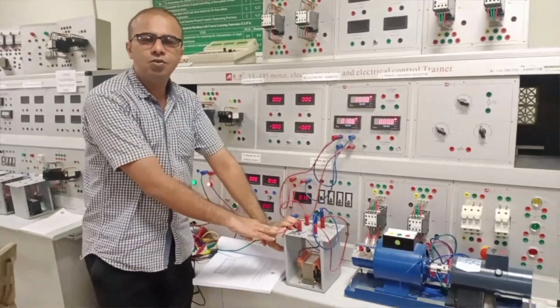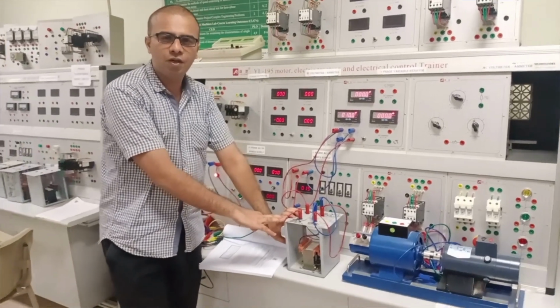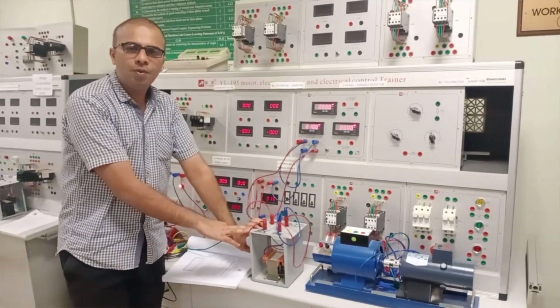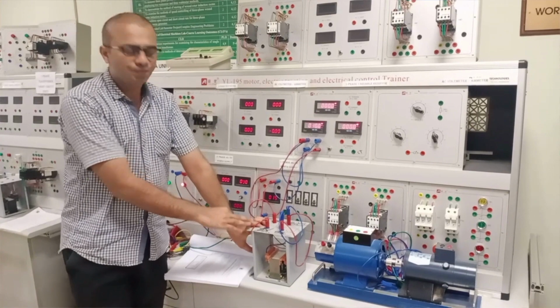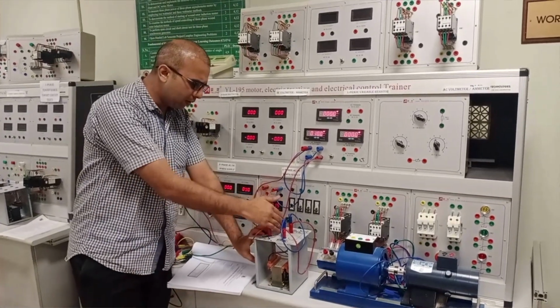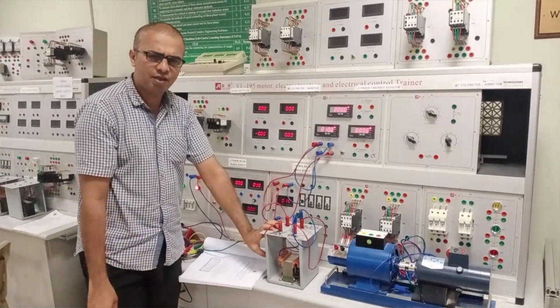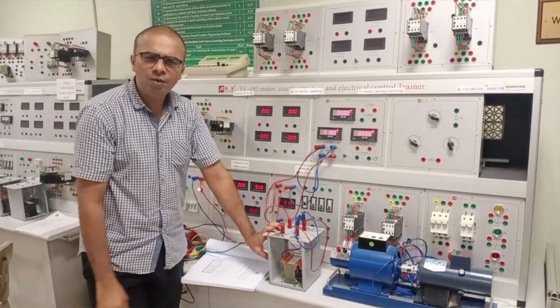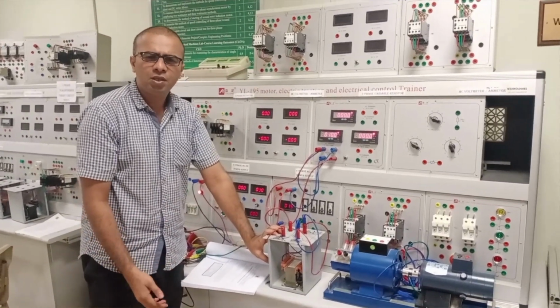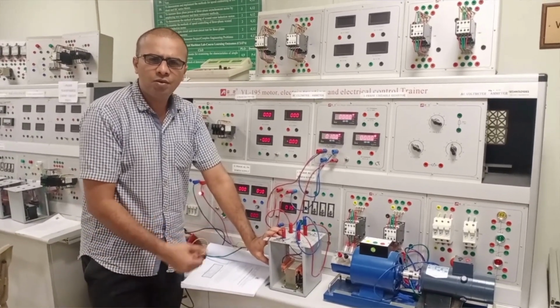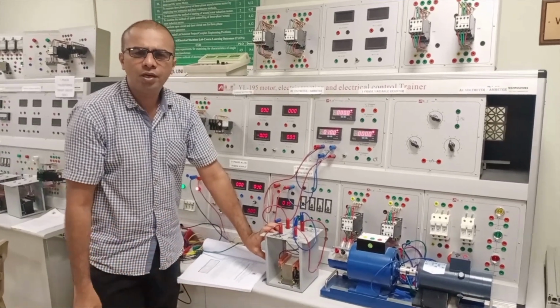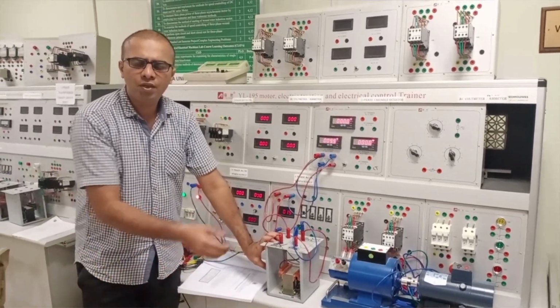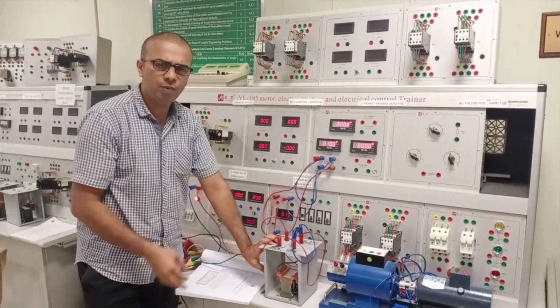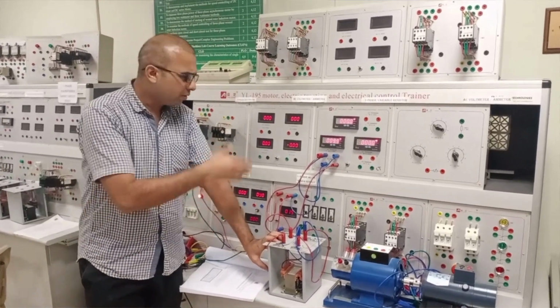The short circuit test is used to find out the copper losses in the transformer, and obviously the copper losses totally depend upon the short circuited low voltage winding. If it is short circuited, obviously when we apply 5 to 10% of the rated voltage to the primary side, the full load current starts flowing from the transformer, which we have already analyzed through the wattmeter, and our readings have been shown on this trainer.